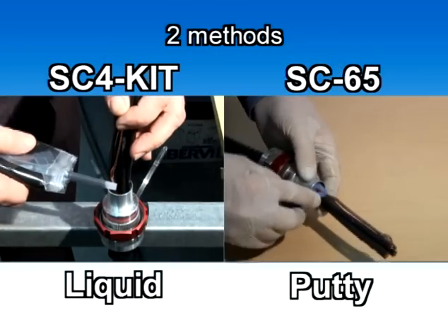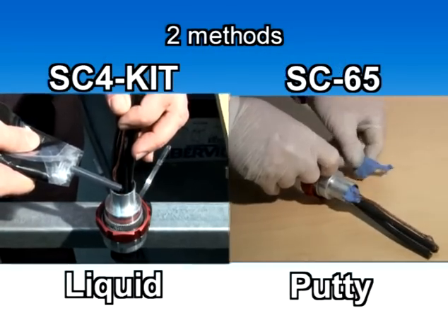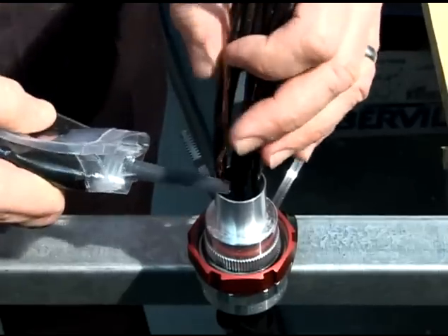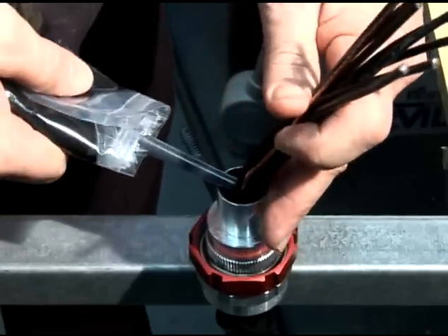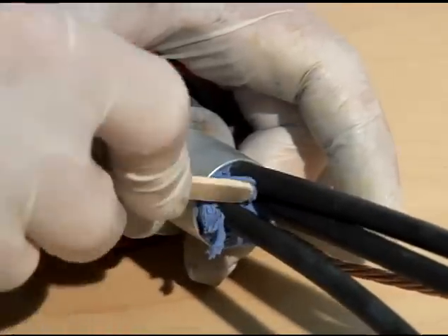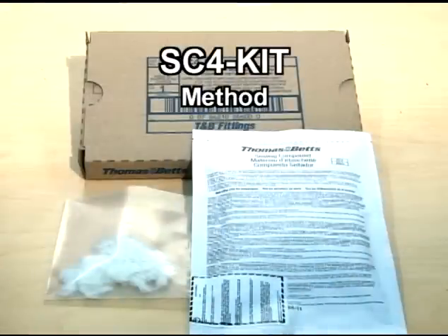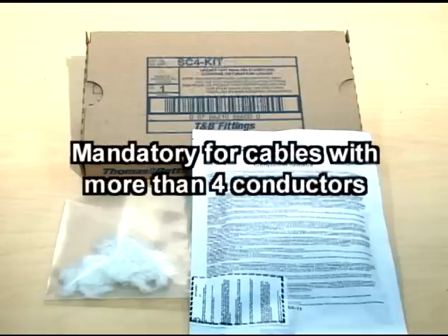There are two types of sealing compounds that can be used when installing the Star Teck XP: the SC4 Liquid Kit, suited for the installation of TECK cables with multiple conductors, and the SC65 Compound, ideal for the installation of TECK cable using four conductors or less. The SC4 Kit Liquid Sealing Compound is recommended for all explosion-proof installations using Star Teck XP fittings and is mandatory for cables with more than four conductors.